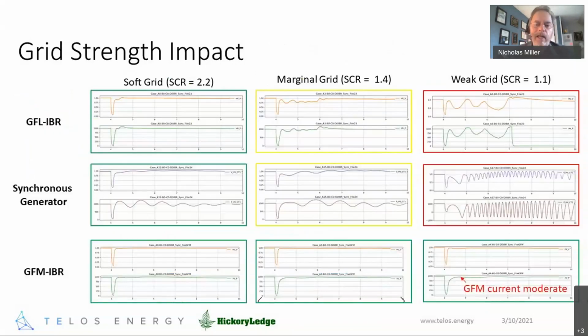I did have another point to make on that slide. Matt made a comment about the currents and ratings of this equipment, and we're going to make a few comments about that at various times. But to get this stable behavior across the bottom with the grid forming inverter did not, I want to emphasize, require us to alter the current rating. We went to great pains to make the GFL versus GFM comparison apples to apples. This good stability behavior, for this event and this setup, with qualifications, does not require beefing up the current carrying capability beyond what you'd expect for this class of equipment. We think that's pretty important. We're not saying don't worry about the current, we're saying it doesn't look like you need a lot of current capability to get this good stability behavior. Pretty important finding. Okay, let's go on to the next slide.